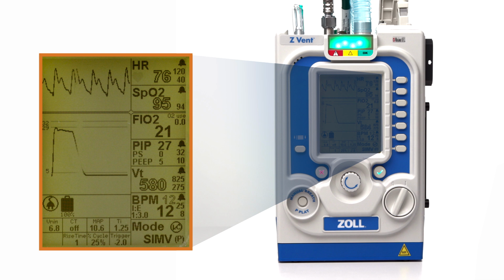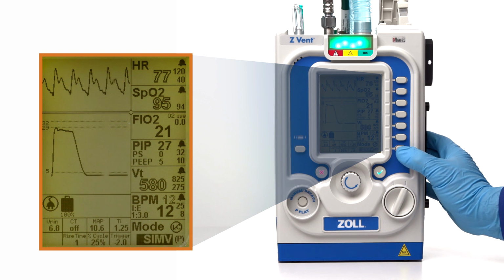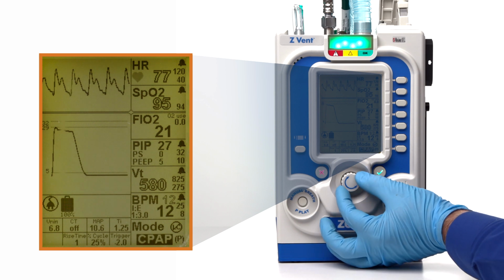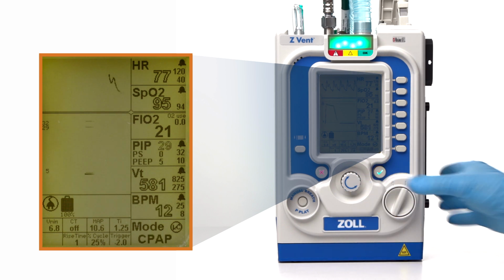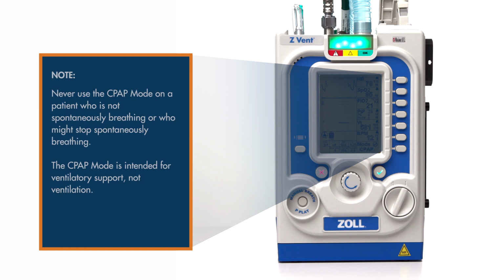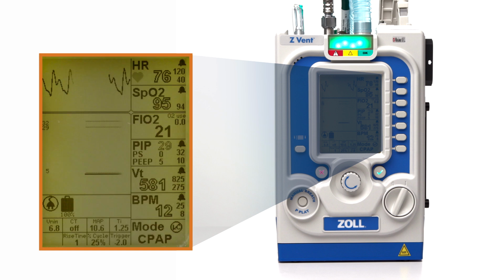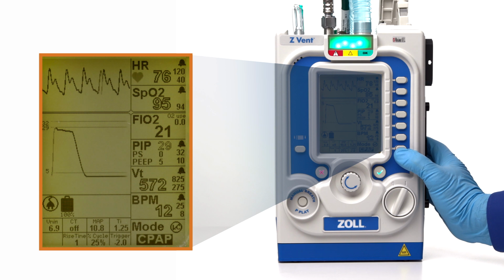In continuous positive airway pressure, or CPAP mode, the patient receives constant positive airway pressure while breathing spontaneously. Never use the CPAP mode on a patient who is not spontaneously breathing or who might stop spontaneously breathing. The CPAP mode is intended for ventilatory support, not ventilation. CPAP can be used with or without leak compensation. When leak compensation is enabled, press the parameter button three times to adjust the leak compensation setting.